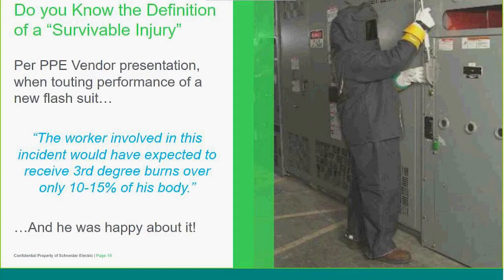So we're still placing ourselves at risk even if we kit up to the highest forms of PPE. In fact, in some instances, particularly at main intake substations, where the fault level is very high and it's fed from a utility company which typically has 1-second clearance times, the incident energy levels are above any PPE ratings that you can buy.